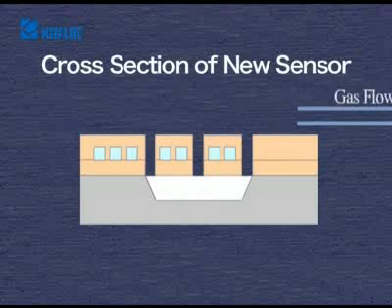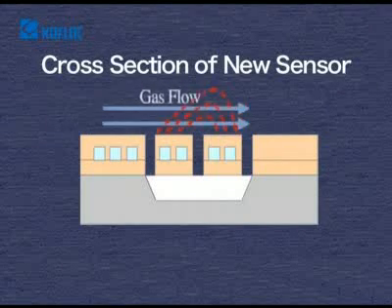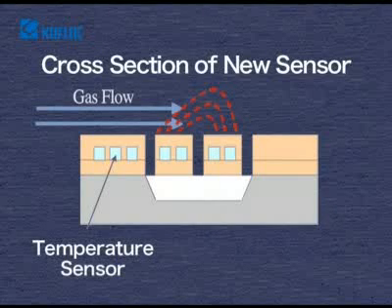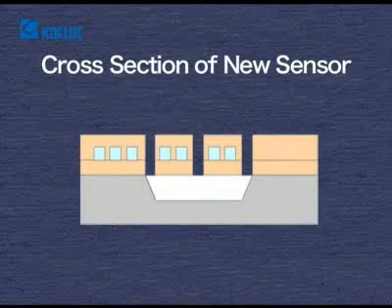When gas flows, the temperature distribution in the heater section changes in the manner shown here. This change in power is detected by the bridge circuit and is taken out as a flow signal.